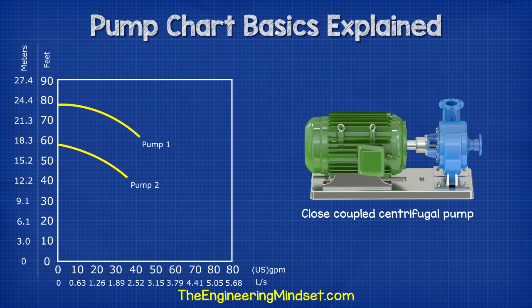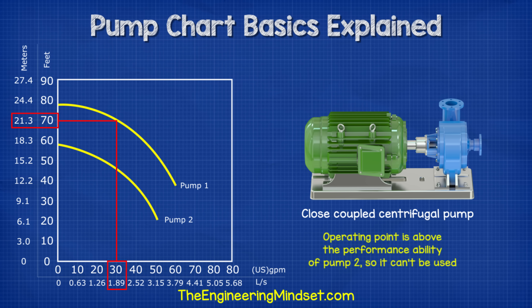For example, the performance curves of two large centrifugal pumps are plotted here. We need a flow rate of 30 gallons per minute and a head pressure of 70 feet. That means that pump two can't be used, but pump one could be.